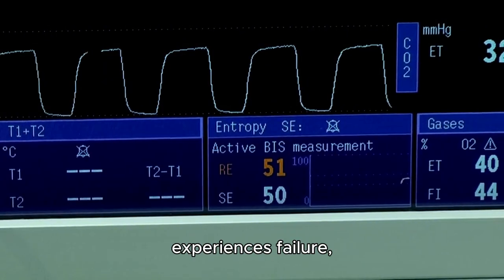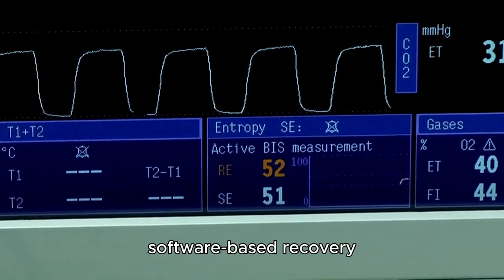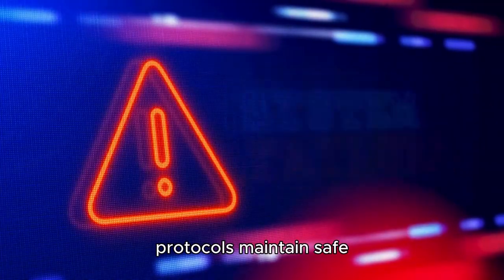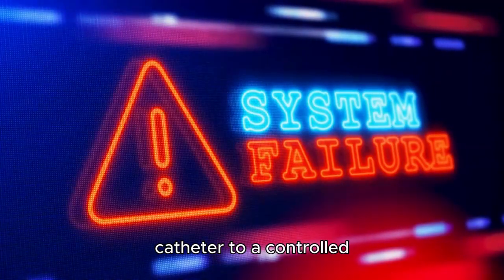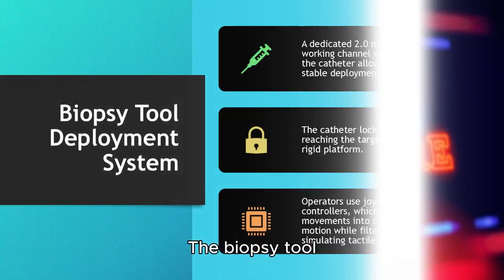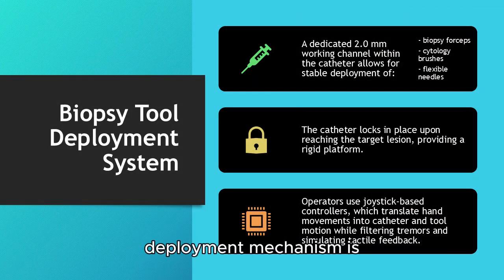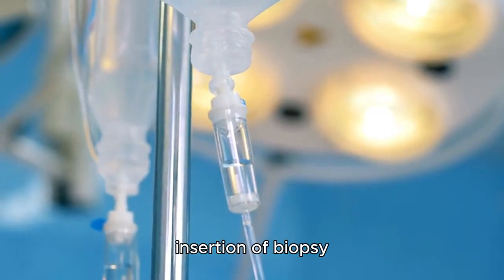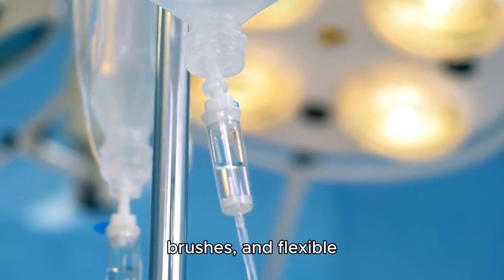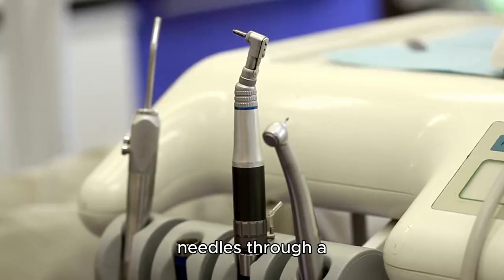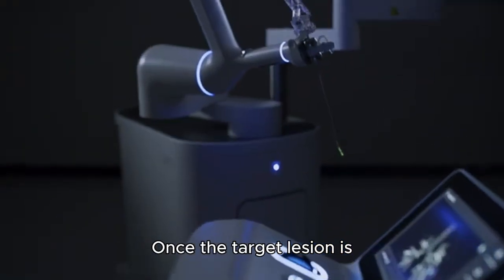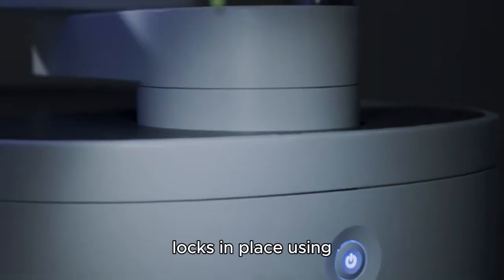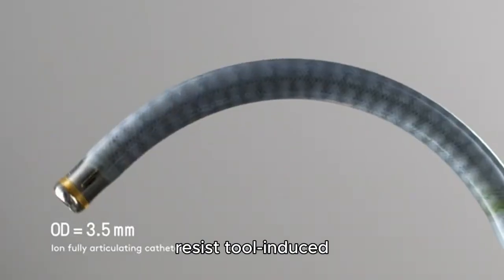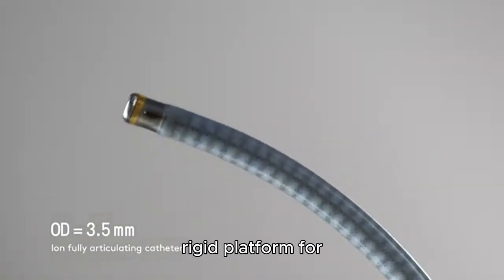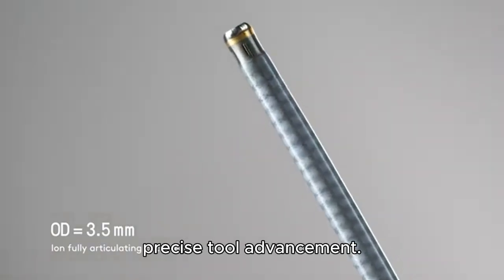If a sensor or actuator experiences failure, backup systems and software-based recovery protocols maintain safe operation and guide the catheter to a controlled withdrawal. The biopsy tool deployment mechanism is integrated into the catheter system, allowing for stable insertion of biopsy forceps, cytology brushes, and flexible needles through a dedicated 2.0 mm working channel. Once the target lesion is reached, the catheter locks in place using mechanical stabilizers to resist tool-induced movement, providing a rigid platform for precise tool advancement.